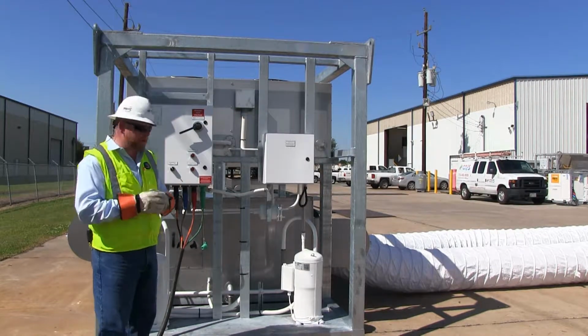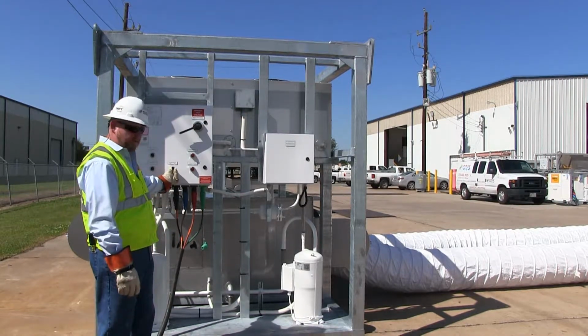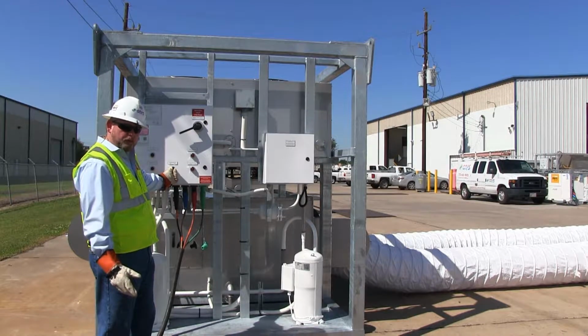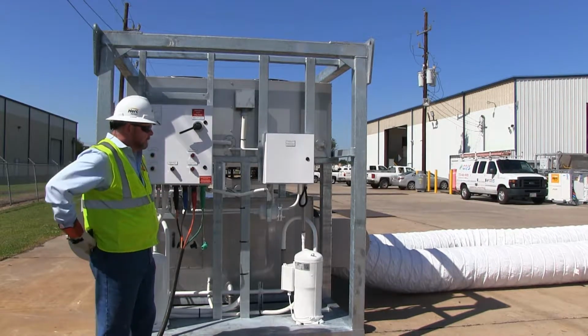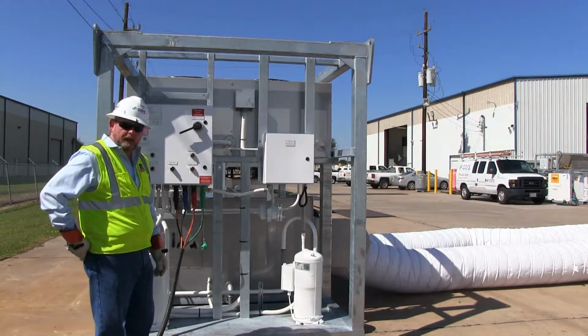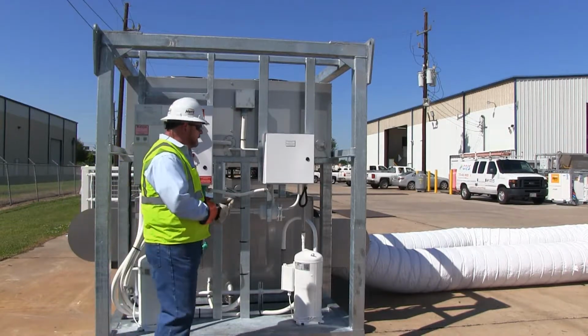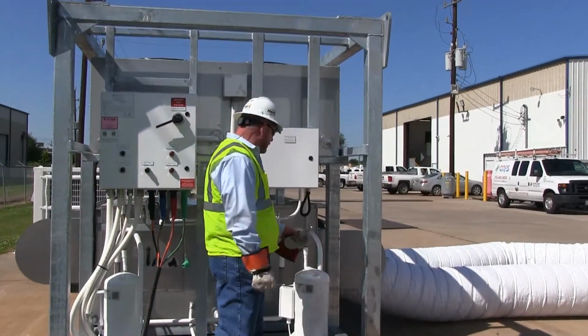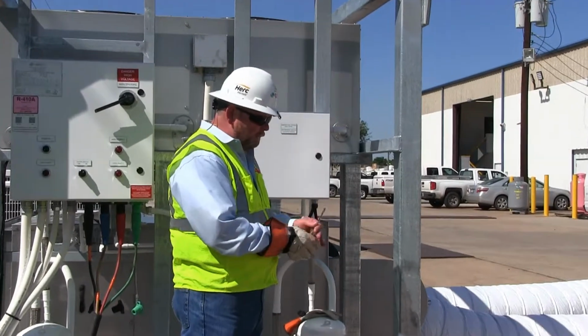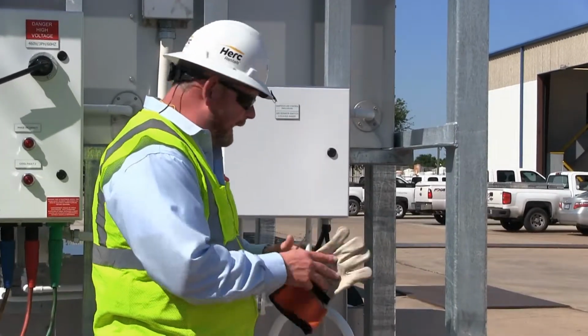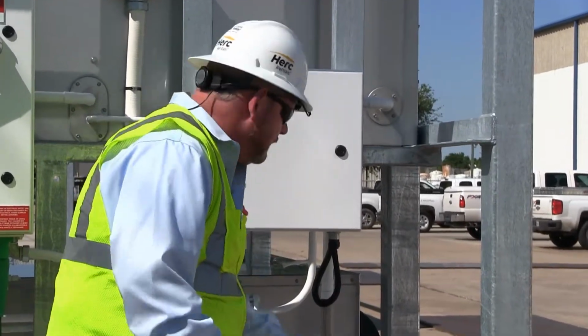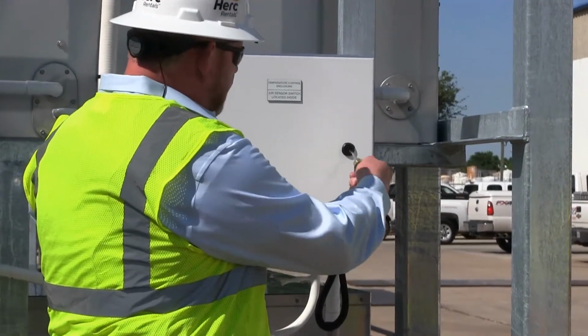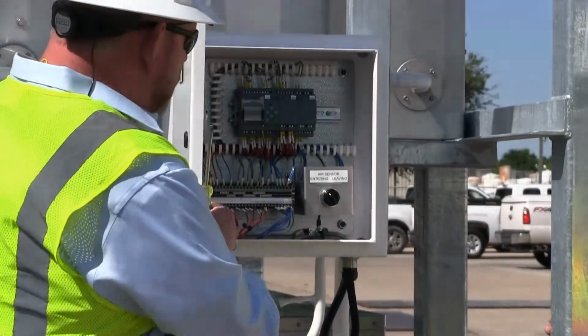It's simply done by energizing the main system switch here. As I turn it on, the indoor fan will come on. There we go. Now we have full airflow. The second part is coming into the temperature control enclosure. This is a low voltage panel, so I no longer need my high voltage gloves. In here, you simply take a screwdriver and open up the control panel.